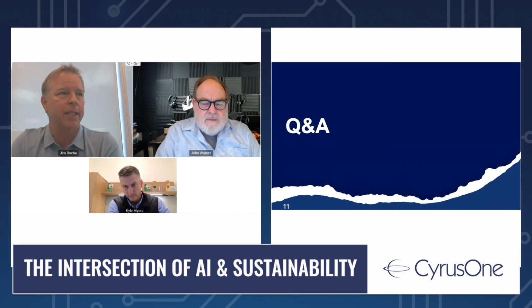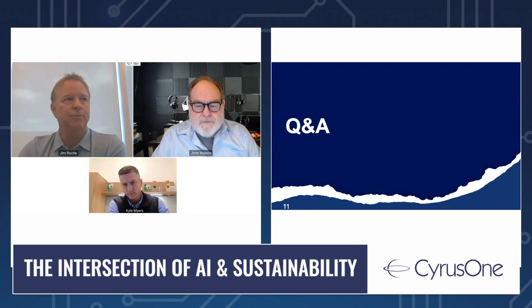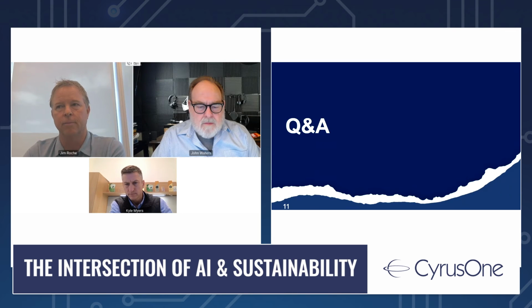I'll take that one. The design is really the same within our data center in that we tap off of the loop system. We use a closed loop system, so we can tap off of that to do liquid to chip, liquid to door, liquid in-row cooling, immersion technology, or run traditional CRAC or fan wall units. So it's not really changing the components and what we're doing from a large standpoint.